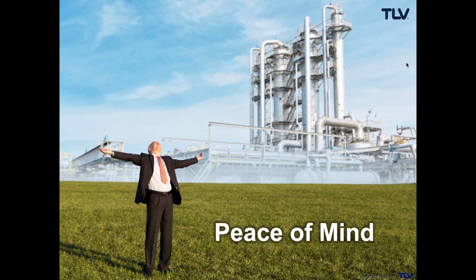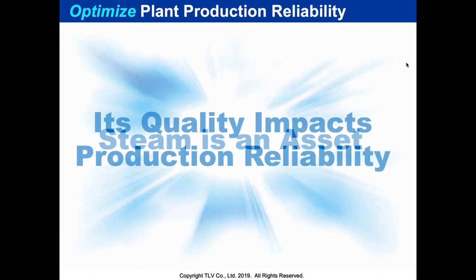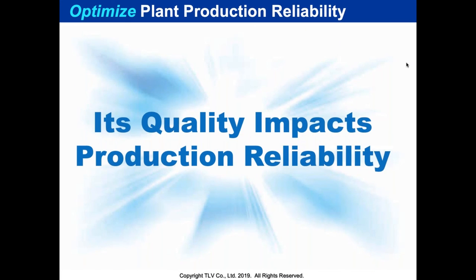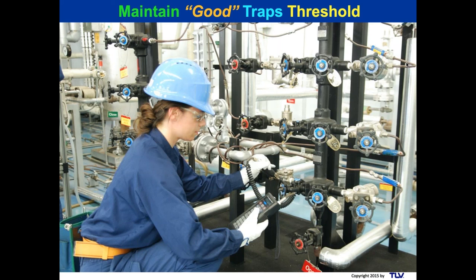Steam is an asset and its quality impacts your production reliability. You cannot optimize your production with suboptimal steam. For things like turbines and flares, maintaining a good trap threshold is critically important. Please use something like TrapMan or another testing system, and fight for the budget money to keep on top of your steam trap population — don't have gap years. Water hammer in your utility mains and steam leaking into returns elevate back pressure, and all kinds of problems follow from trap program maintenance failures.